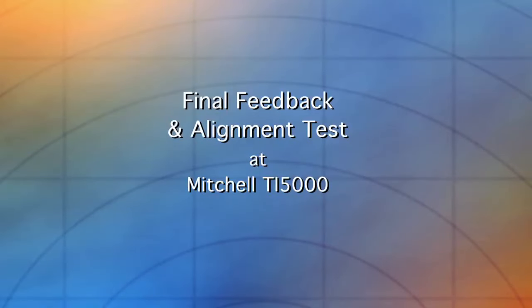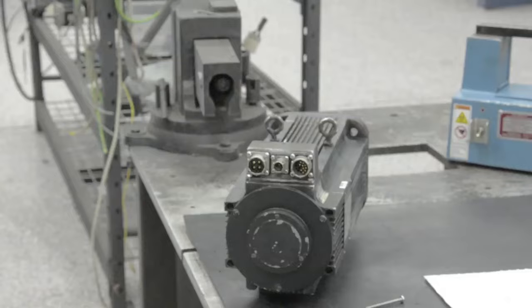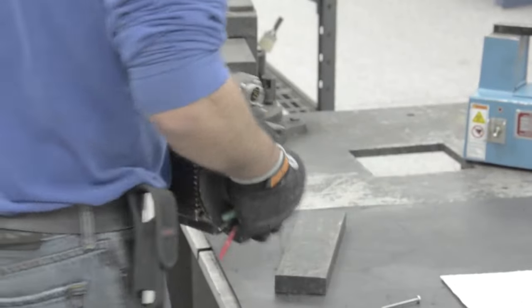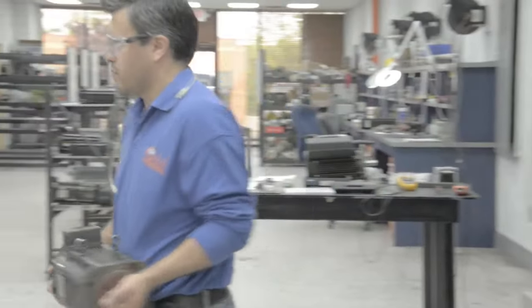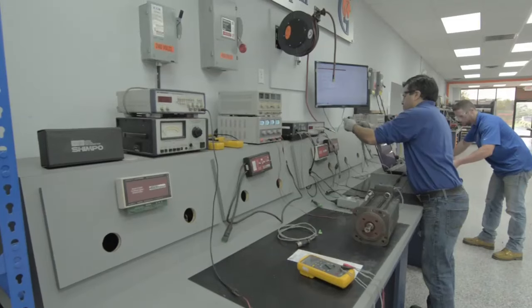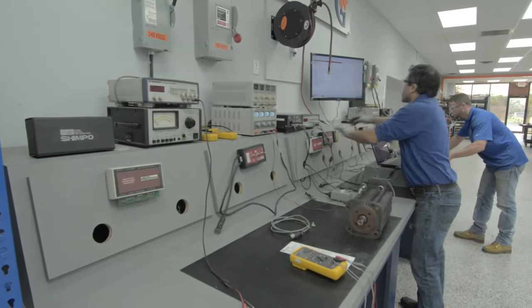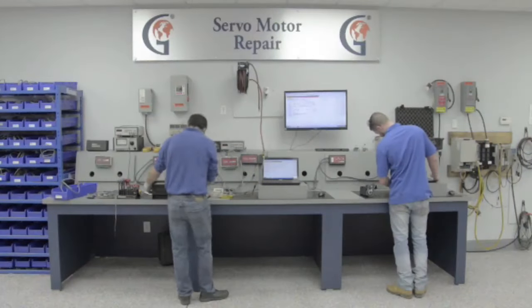Final test at the TI-5000 station. Now that our servo motor has been completely cleaned, dried, had the encoder repaired and tested, and new bearings, it's ready for final testing. Before the final cleaning and paint, we'll retest at the Mitchell Electronics TI-5000 station to ensure the encoder is working properly and to verify its alignment for the final test.